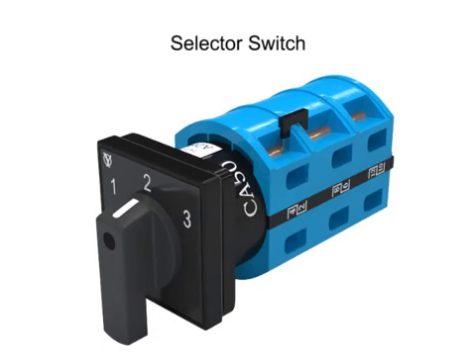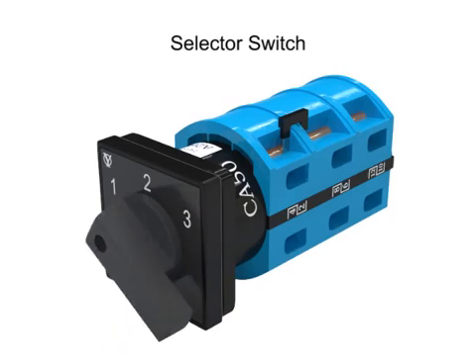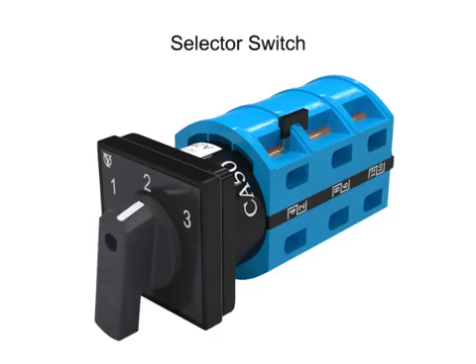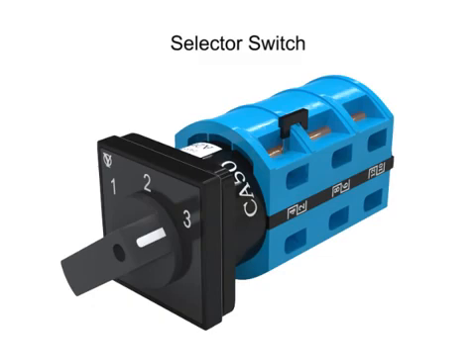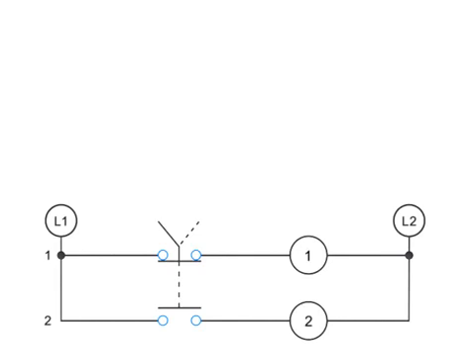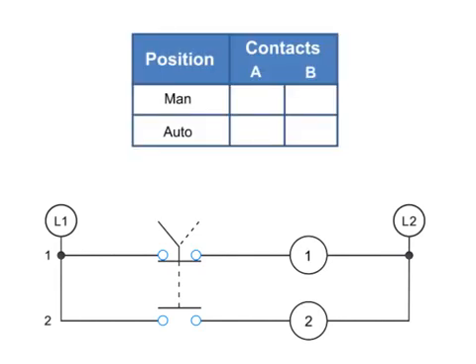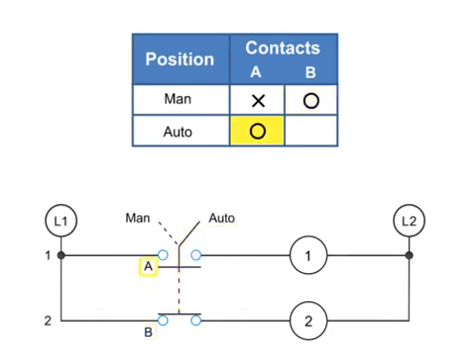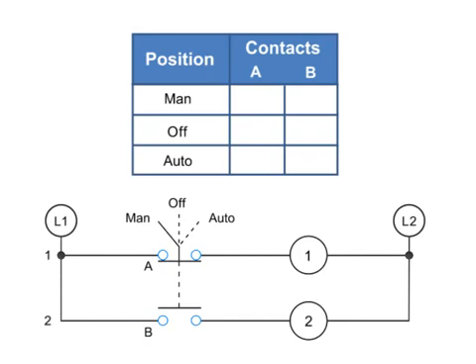A selector switch is a device with an operator that is manually rotated to activate electrical contacts. They are normally used to select either two or three different circuit conditions. Contact position on a selector switch can easily be illustrated using truth tables. This truth table illustrates the manual or automatic contact positions of a two-contact selector switch. If the selector switch is in the MAN position, A is X or closed and B is O or open. When the switch position is set to AUTO, A is O or open and B is X or closed. In a three-position selector switch, a third row is added to the truth table, giving a MANUAL position, an OFF position, and an AUTOMATIC position.